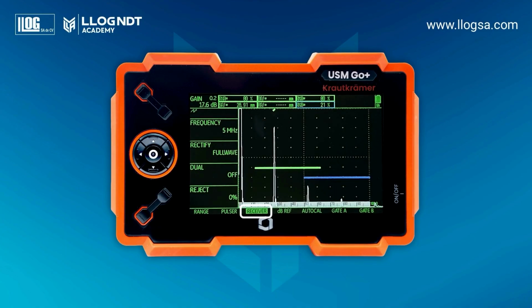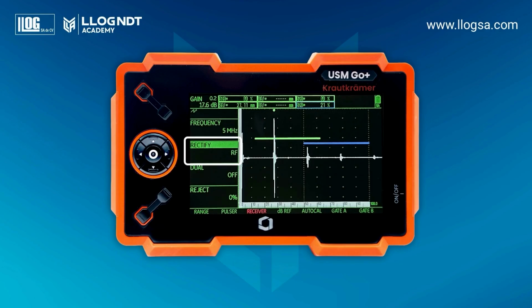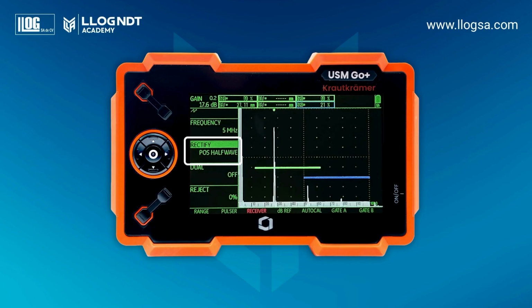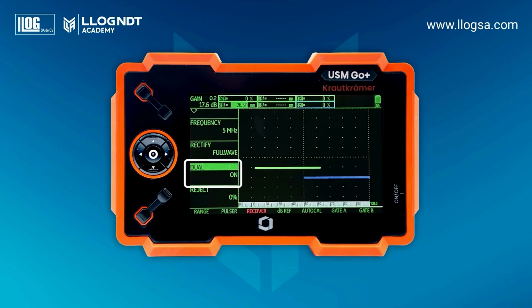The third group contains receiver settings. The first function allows selecting the probe frequency. If the frequency is unknown, you can choose a bandwidth instead. Wave rectification can be set to full wave, radio frequency, negative half wave, or positive half wave. Dual mode should be off when using single probes and on when using dual or double element probes. Through transmission mode is enabled when using 2 separate probes. Reject removes a percentage of echo height from the A-scan display.